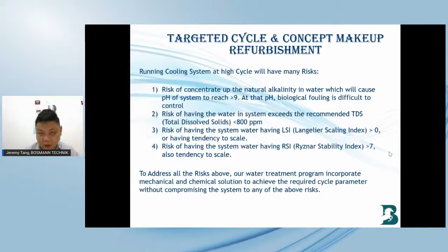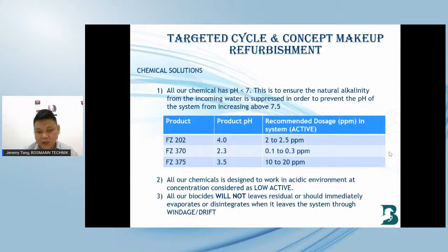Okay, for our chemical, it's all under pH 7. This is to ensure all the natural alkalinity from the incoming water is suppressed, in order to prevent the pH of the system from increasing above 7.5. Because, as we mentioned in the previous slide, when the pH is more than 7.5, there is a tendency to scale and the algae grow very fast. So all of our chemicals are designed to work in an acidic environment, and the concentration is considered low active. It's a slow reaction chemical. All our biocide will not leave any residue and immediately evaporates or dissipates when it leaves the system through the blowdown or drift.